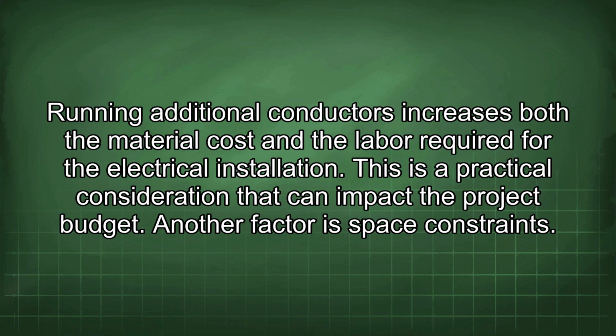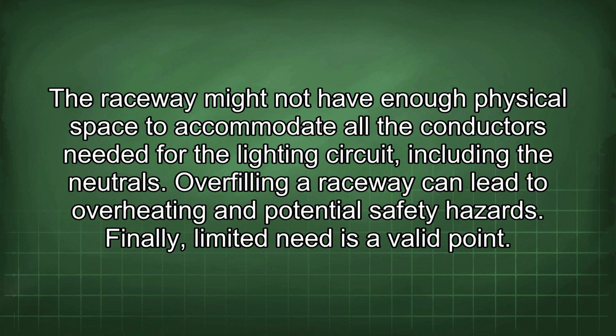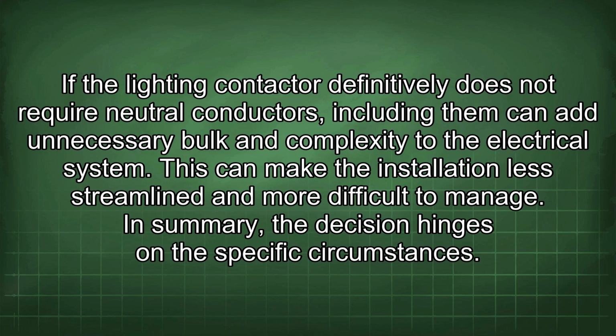Another factor is space constraints. The raceway might not have enough physical space to accommodate all the conductors needed for the lighting circuit, including the neutrals. Overfilling a raceway can lead to overheating and potential safety hazards. Finally, limited need is a valid point. If the lighting contactor definitively does not require neutral conductors, including them can add unnecessary bulk and complexity to the electrical system. This can make the installation less streamlined and more difficult to manage.